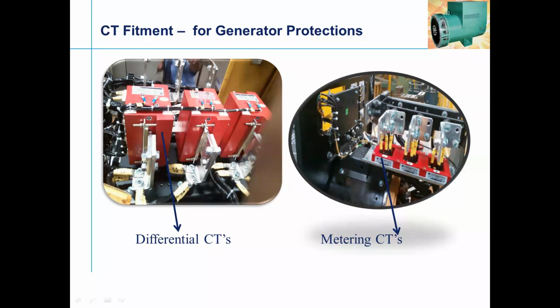This is the differential CT, which is very important. There are two ways to look at the system. One is for the generator safety, another for the human safety. For the generator safety, we do body earthing and more of the winding. If you want to protect a generator from damage due to any surge voltage or surge current, this differential CT is very, very important.